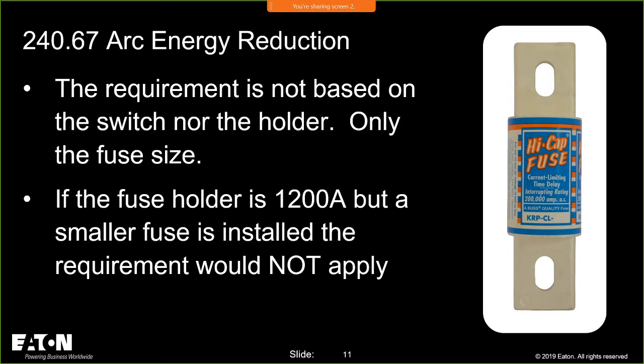Okay, so the requirement is also not based on the switch nor the holder. It's the fuse size, because it says where you have a fuse, not fusible equipment, not a fusible switch, or anything like that. A fuse holder can be 1,200 amps, but if I put an 800 amp fuse in that fuse holder, I do not fall under the requirements of 240.67 just because I have a fuse holder of 1,200 amps. It's keyed on the fuse.